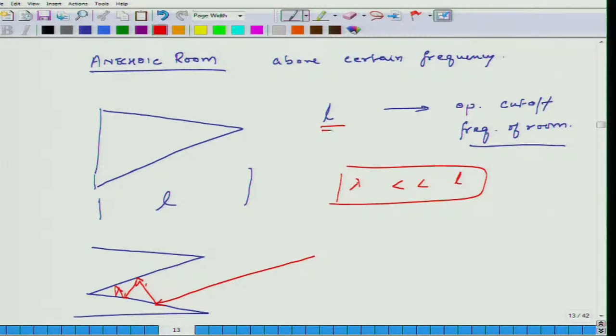The size of these cones is extremely important. If I want my anechoic chamber to work at low frequencies, the cones have to be very large. If the chamber only needs to work at maybe 500 Hz and above, then I do not need very large cones. That is the basic operating principle of these anechoic chambers.